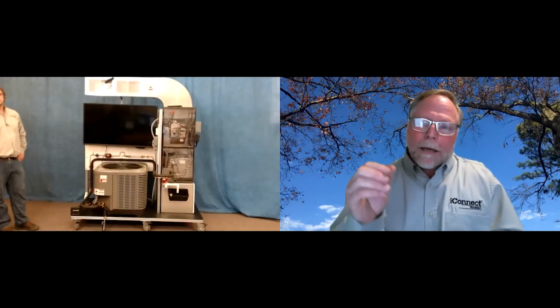So that's lesson number one: when we kill the condenser fan, how does it affect the refrigerant cycle? And secondly, what are some of the things that would cause that condenser fan to go off? Then we'll flip the switch back on, fix the fan, and watch the pressures come back up. Currently, as we look through that, the second lesson is talking about what heat transfer actually is.